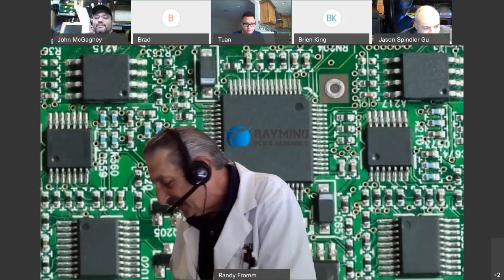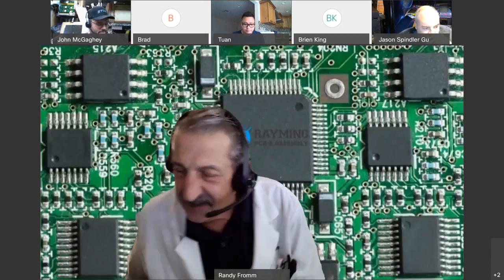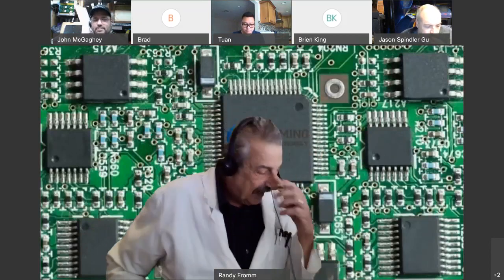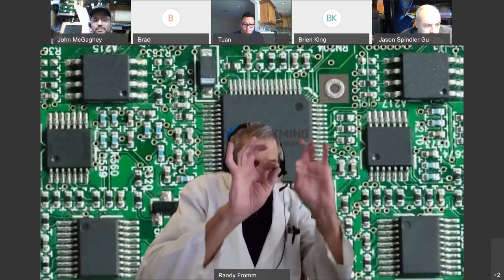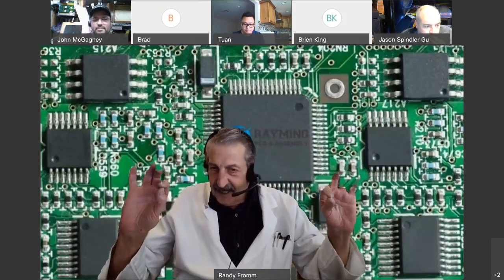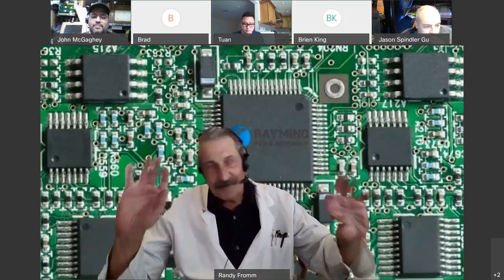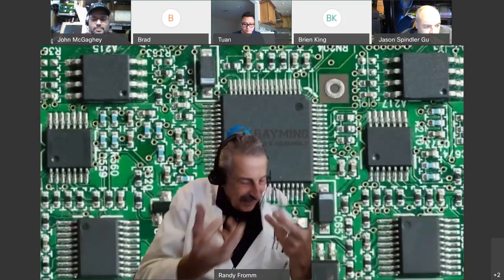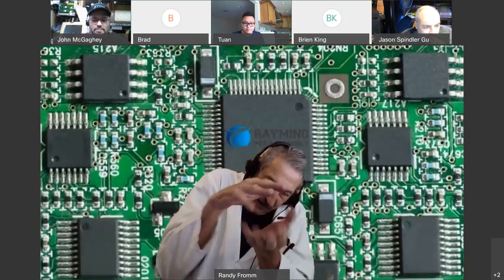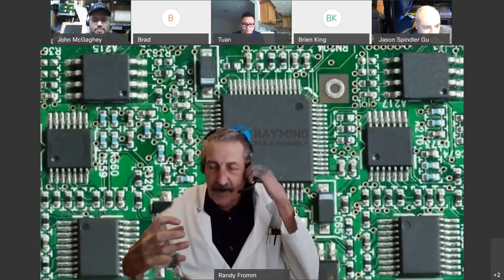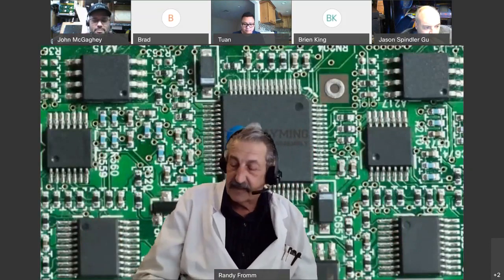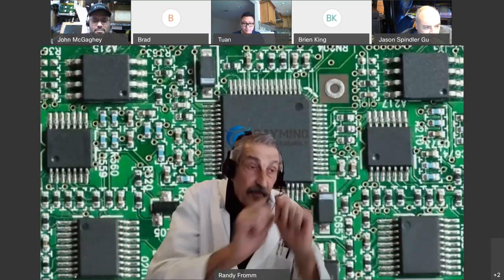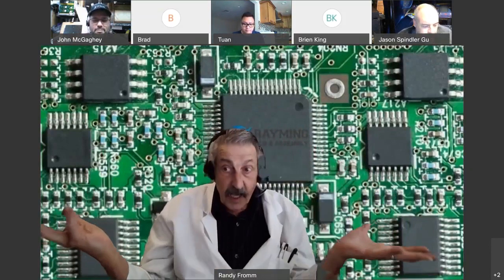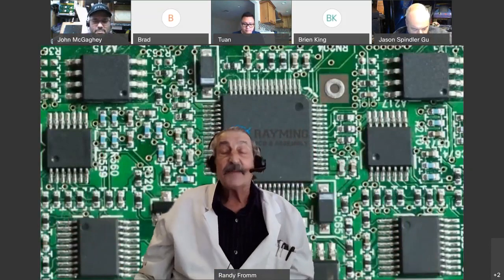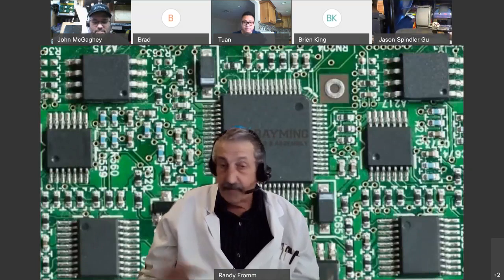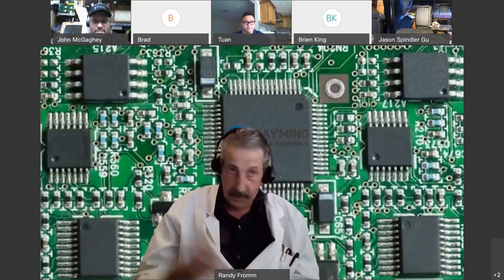Just because something is grounded doesn't mean there's nothing on it. If I have a thin conductor as my ground conductor, I can have all kinds of weird noise on it, unless it's really well connected to earth ground. There's noise on things, and that's why we typically connect that other earth ground. But does it have to be there? No. And does it prevent a shock? No, not as far as I know.